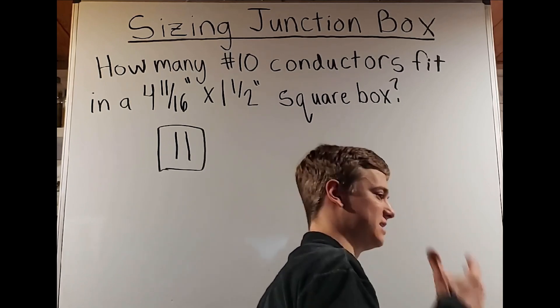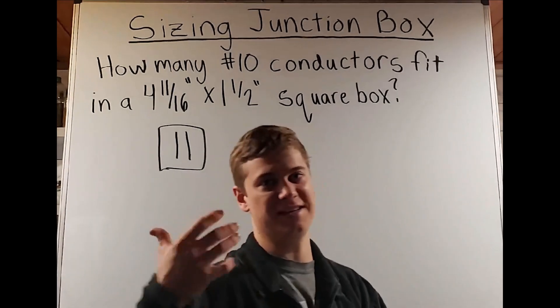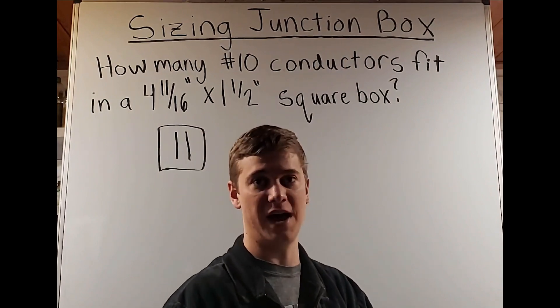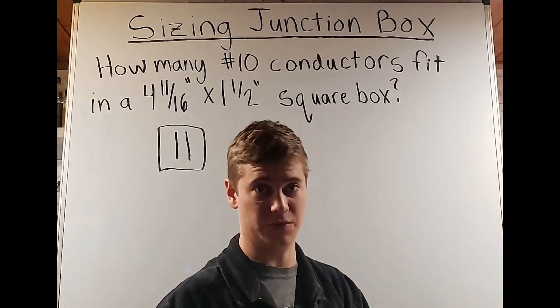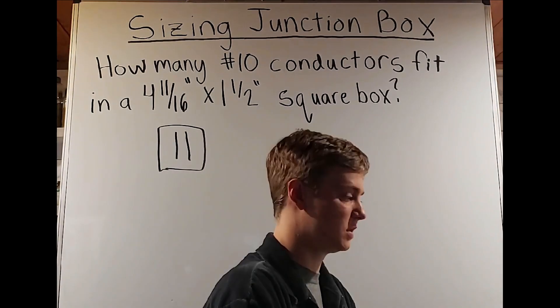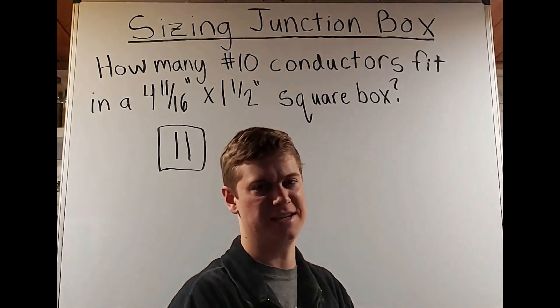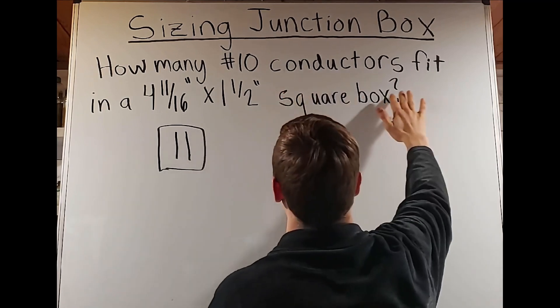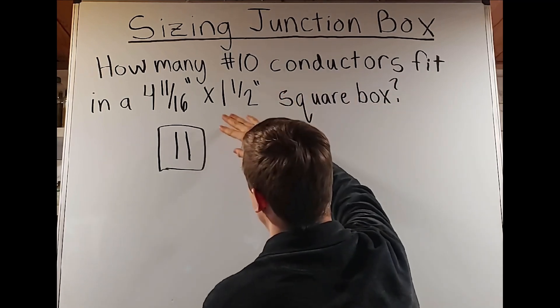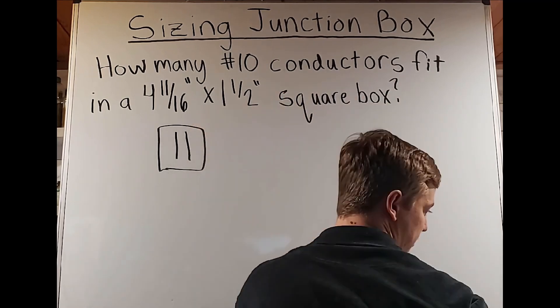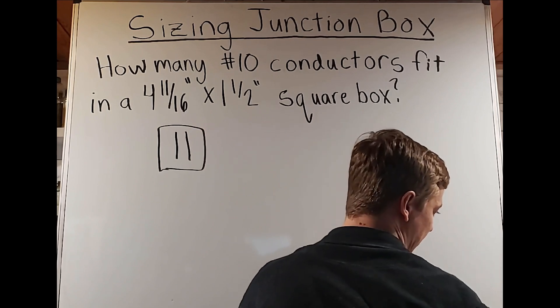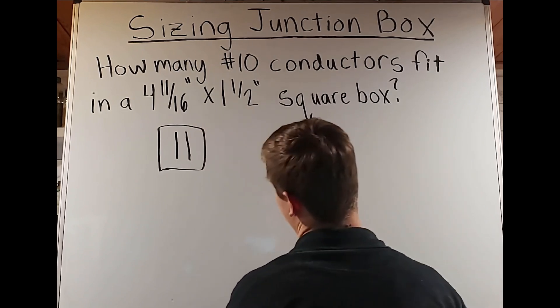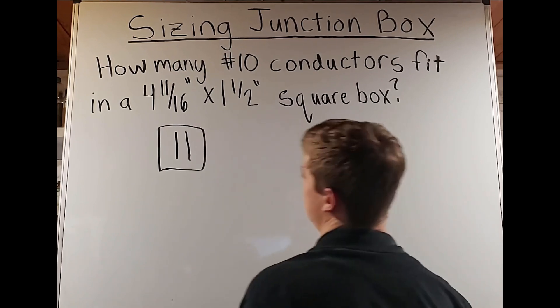You can compare this to using Annex C instead of Chapter 9 Table 5 and Table 4 to figure out your conduit fill — this table serves as a similarly efficient method. When you know the gauge of your wire and the size of the box, the table already tells you how many conductors of that size will fit in that box. This will come in handy for some other things as well.